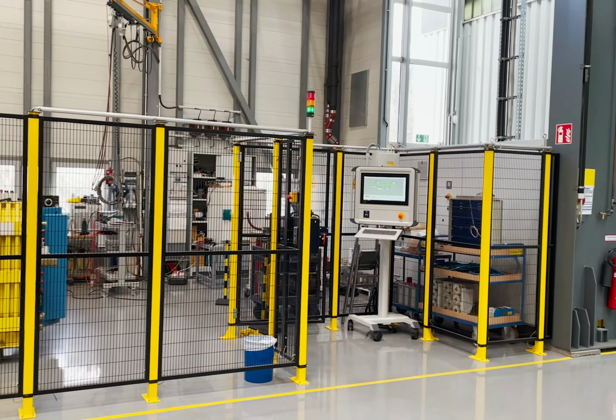In this secure fenced-off area, we carry out high voltage and high current tests to inspect input control of components for production and perform final tests before delivery. Here we also research and develop tests for new developments. The high voltage test facility is equipped with a 12 kV generator where voltage is adjusted via the control panel to supply voltage for the needed test requirements.